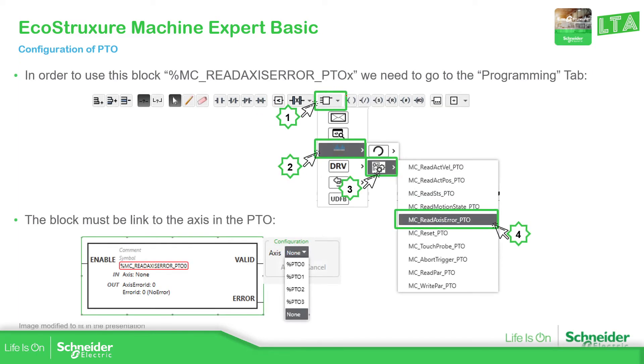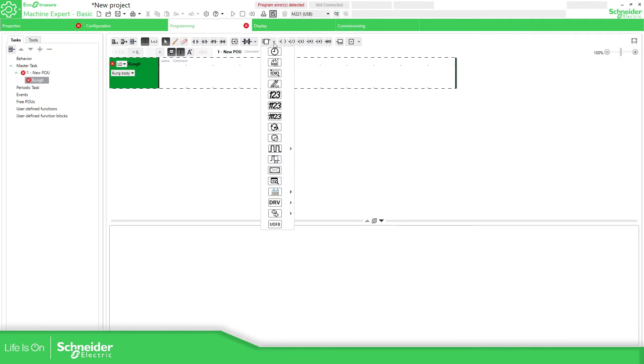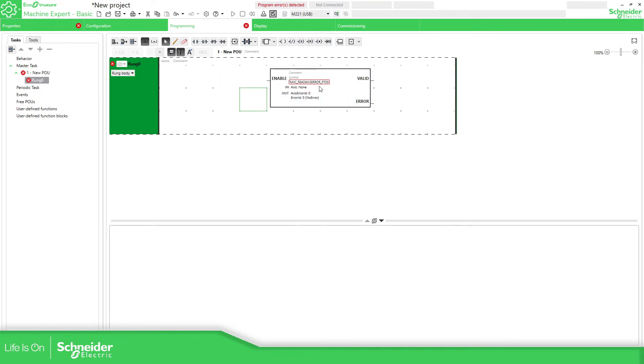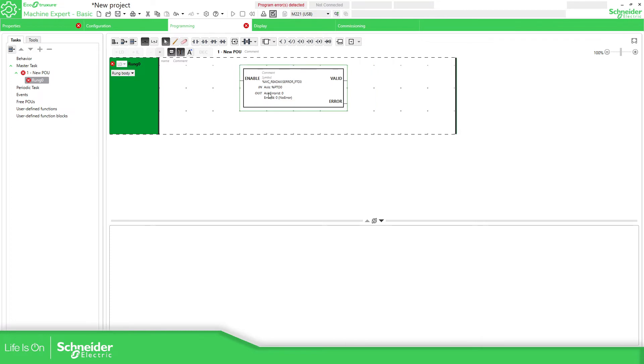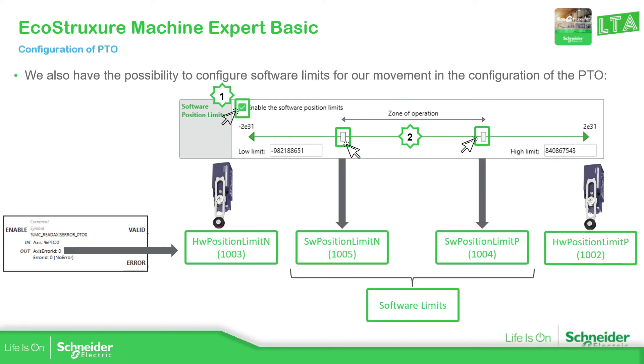To add the Read Axis Error block, we go to the programming tab. Under Motion and then Administrative, we have the possibility to select Read Axis Error. Once it's placed, we just link it to an axis — for example PTO zero — and apply. Then we can read the Axis Error ID, which will show one of the error values corresponding to reaching a configured limit.